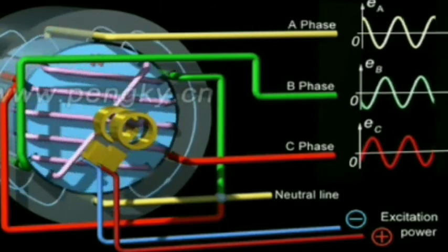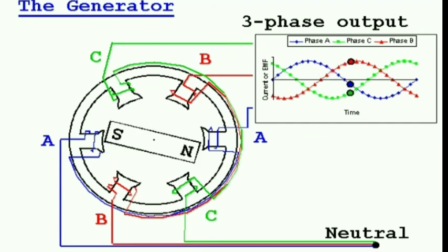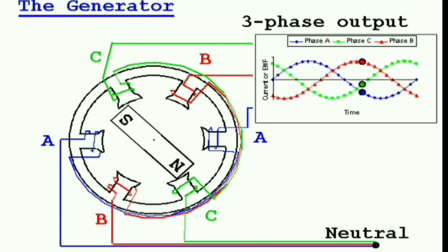We give DC power, which is called excitation power, to the rotor winding or field winding through the carbon brushes and slip rings. We can control the output voltage of the AC generator by controlling the excitation power through the DC power supply through the variable resistance. The AC generators are of two types: self excitation and separate excitation.